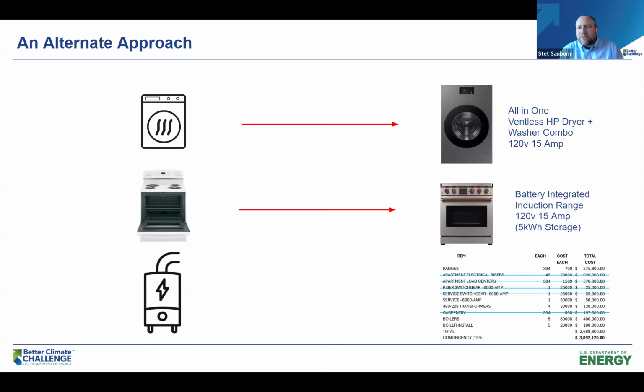So when we look at that horrible, scary $3 million cost for this particular project, all of a sudden we can strike out the electrical riser upgrades, we can strike out the new load centers, we can strike out, for a good chunk of this, the new switchgear that was going to be required to support all that electrification upstairs. And that's just through thoughtful equipment selection. Now, it's true, these two pieces of equipment cost more than your off-the-shelf typical electric range and electric resistance dryer, but with far less disruption, not having to rip up the entire building and potentially move folks out while you take power off and re-energize the building. So a much lower cost of entry and a lot less impact on the project.